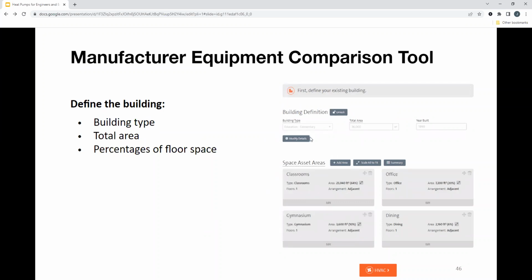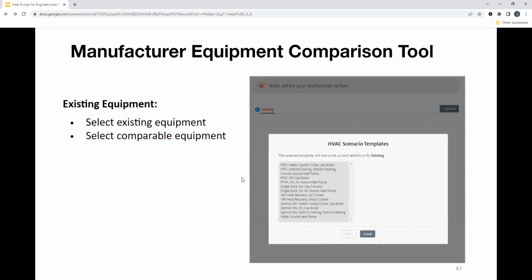So let's say I'm dealing with an elementary school. So I have about this many square feet of classrooms, office square footage, I have about 7,200 square feet. Gymnasium takes up 3,600 square feet. And then there's a cafeteria or dining. So you break it up into different areas like that based on usage of the school. And then you can go into existing equipment, right? So I can take a system that has a central VAV with a water-cooled chiller and a gas boiler, select that. And maybe I want to compare VRF, this existing system, and an additional system, so I can select one of those.